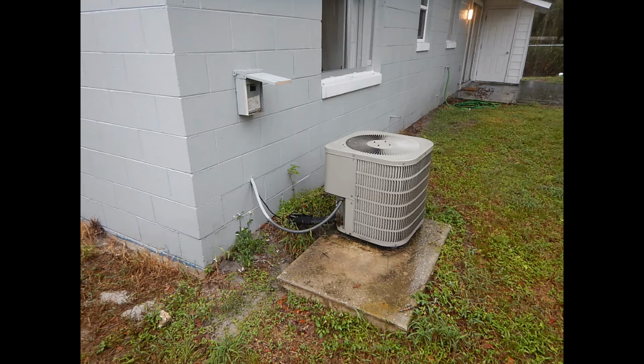There was some legal action taken against certain coils back in 2014 - I believe it was Lennox. If you're not opening up the air handler unit to look at the coils, and you've got a unit from that era in really bad shape, you'll want that in your report. Being informed about that lawsuit is a plus for your client, because if there's any recourse for them, they may be able to go through that class action settlement.